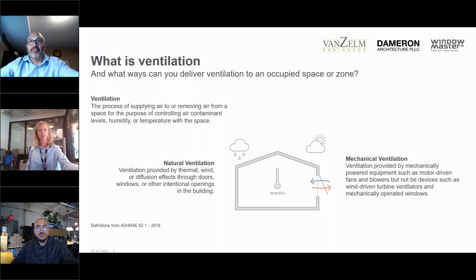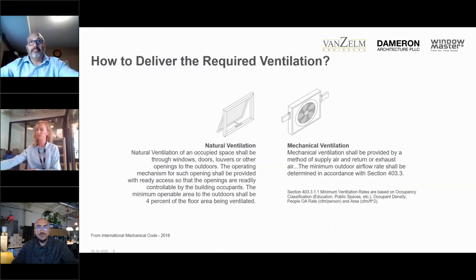You have natural ventilation and you have the mechanical ventilation means. Natural ventilation is obviously using direct outside air through the use of openings in doors, windows, or other openings in the building, could be louvers, but you do it naturally without the process of mechanically moving it. And on the flip side of that, obviously mechanical ventilation, it's providing ventilation through mechanical means, through a fan or an air handling unit or a blower to get it within the occupied space. So there's really two main methodologies of how to get that outside air, which is the benefit for everyone, into the building. So again, how do you deliver the required ventilation?